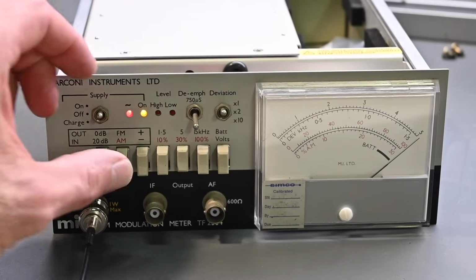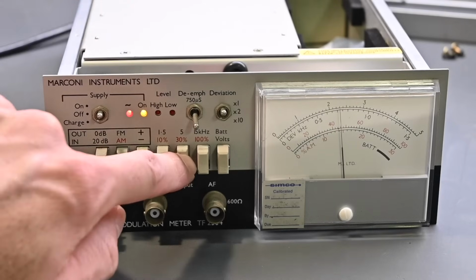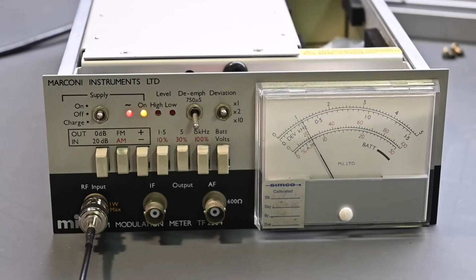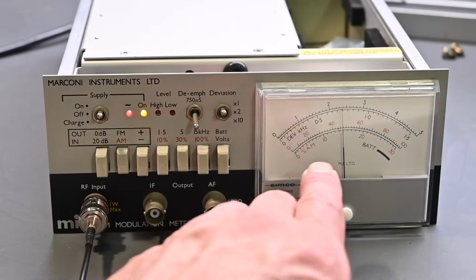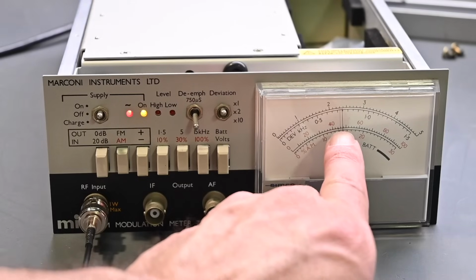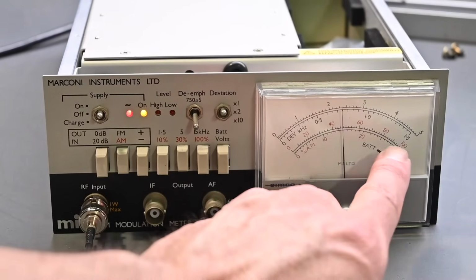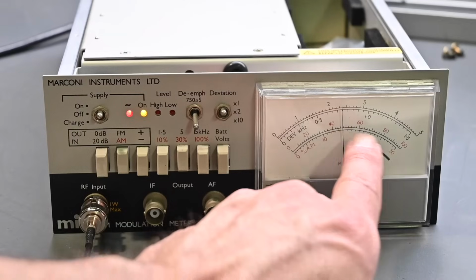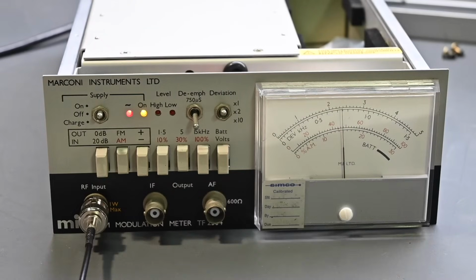Now on the AM, if I go over here, AM, leave this alone, so that's on 30% full scale. Turn the FM off, turn AM on. And right now that's sitting at 16% modulation. And you can see that's essentially right on the 15%, because this is 30, so half would be the 15 right there. It's on the bottom red scale. So, it's 1% off on the modulation number. I mean, that's extremely close at this point. So I don't think it can be dialed in any closer than that.